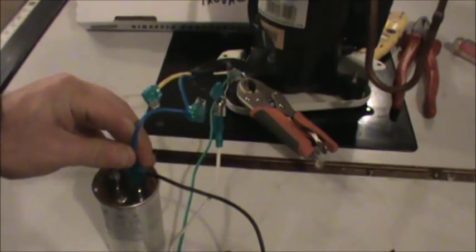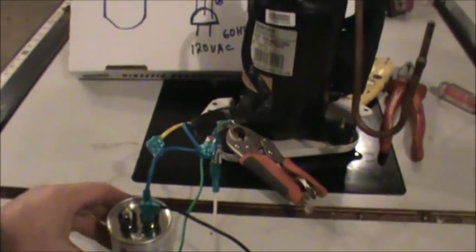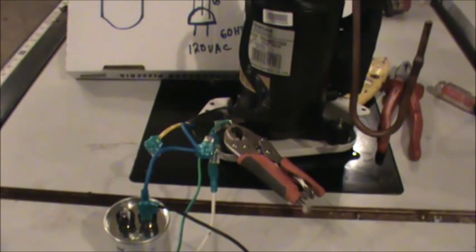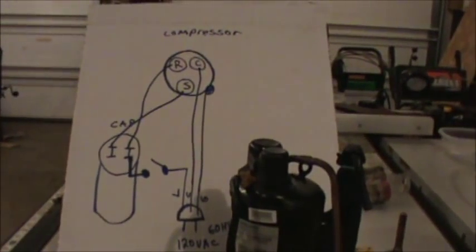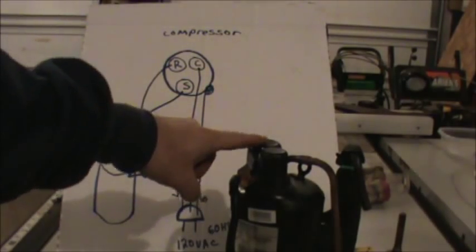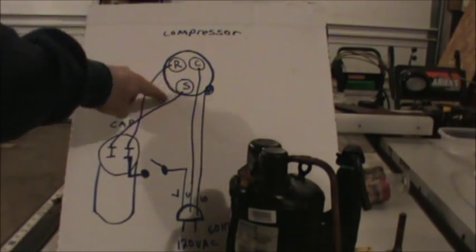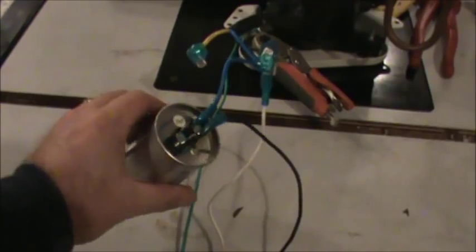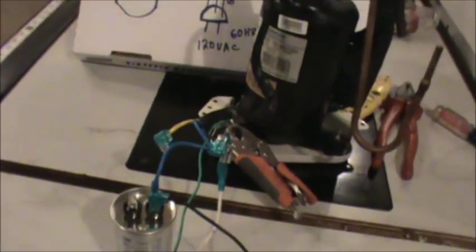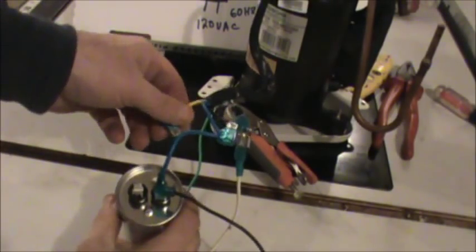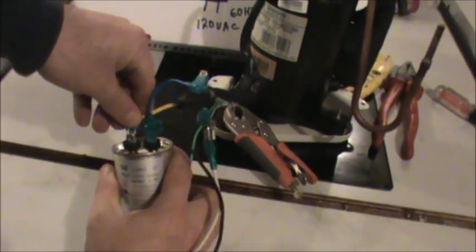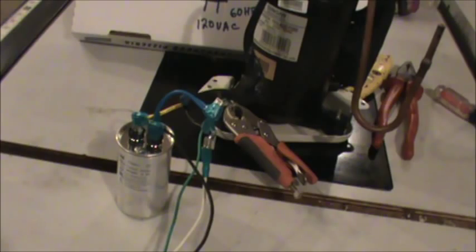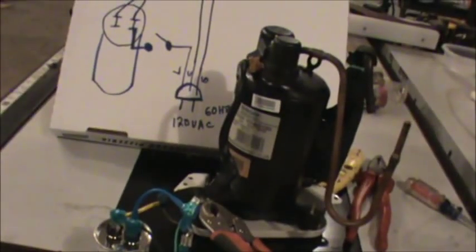Our blue wire is going to go onto the capacitor like that. And the last run we need to make is for our start wire. And our start wire basically goes from the start on our compressor out to the other lug on the capacitor. So it could basically go to either of these two terminals. So we are all wired up, and we're going to plug this thing in and see if it works.